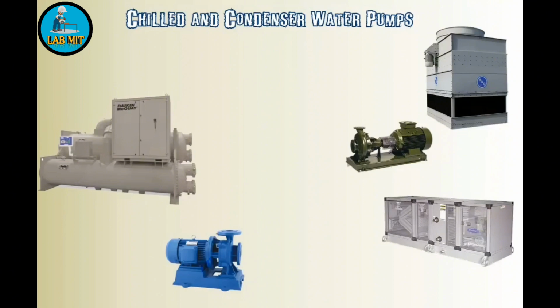Alright, we're going to draw the chill water piping coming out of the chiller with the light blue because it's freezing cold. And we're going to draw that coming into the bottom of the coil. And that's actually kind of important. Typically you want to pipe in the incoming water going to the bottom of the coil.